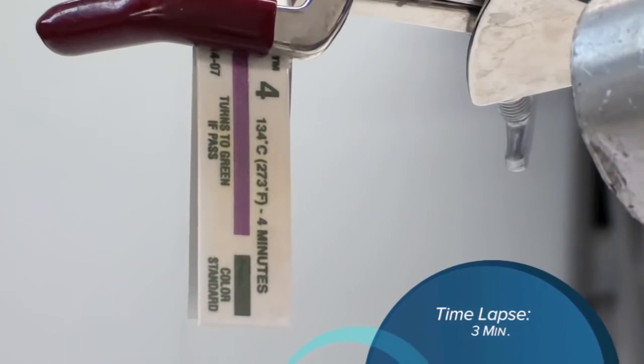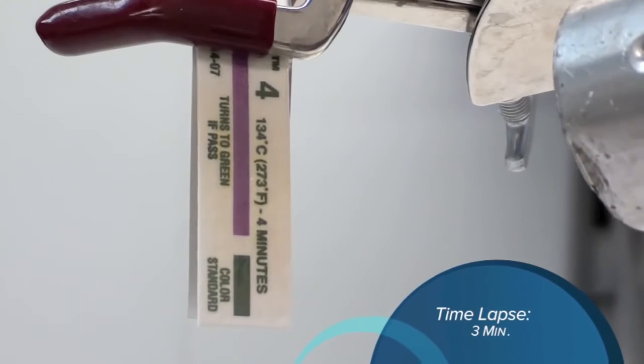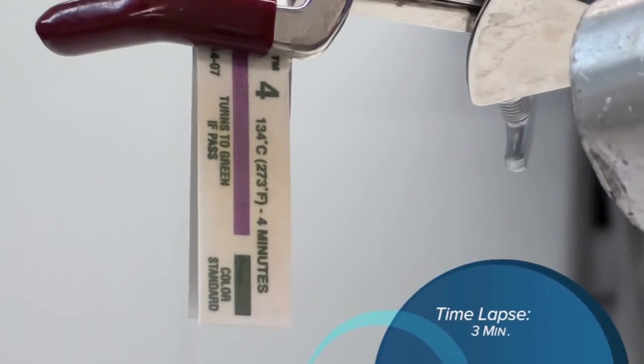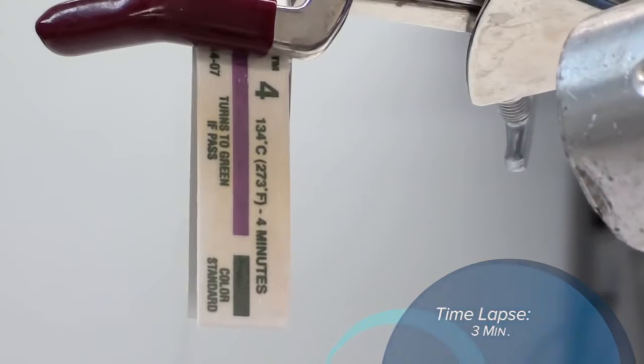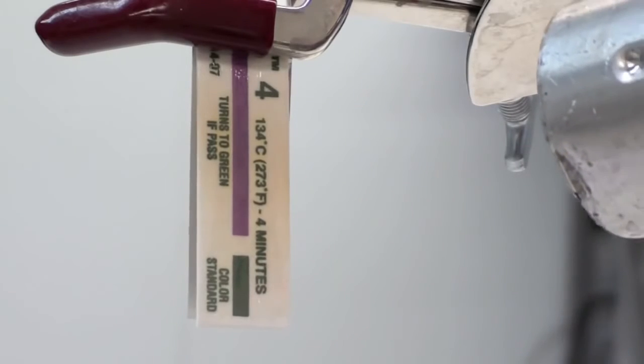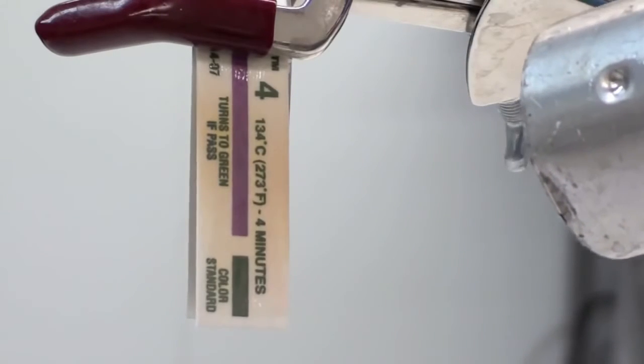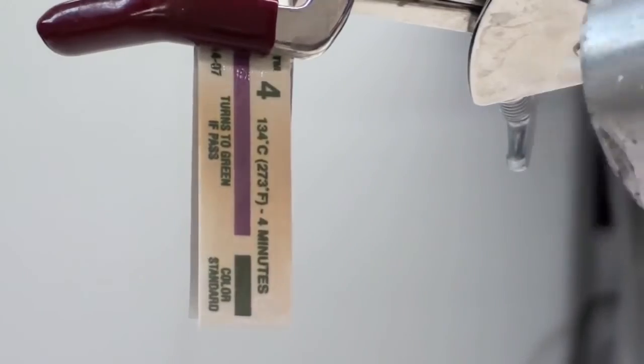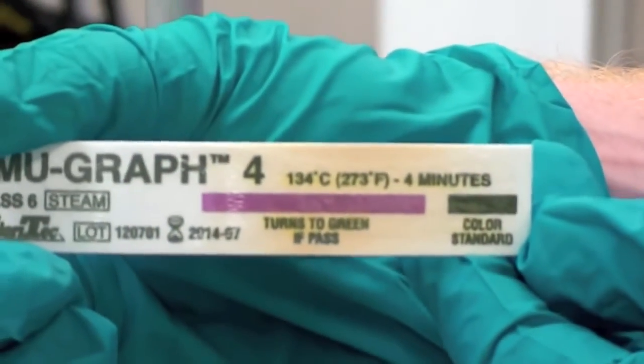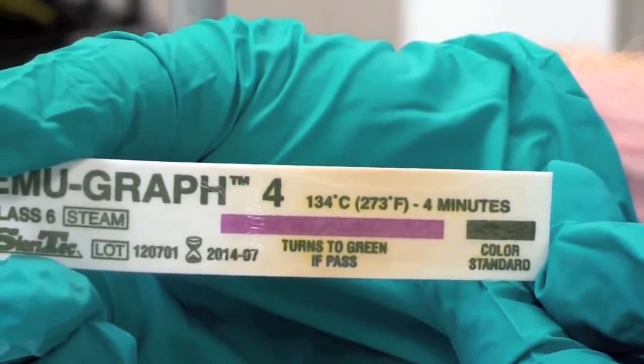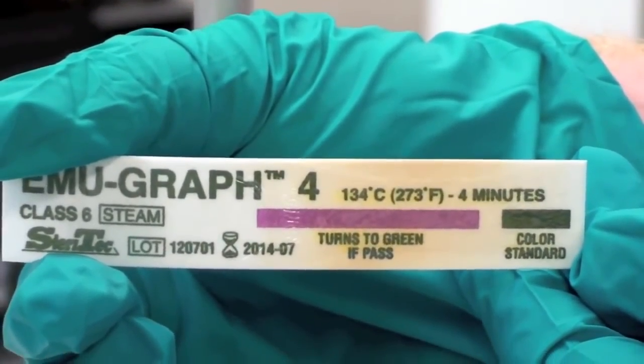We applied dry heat exposure to this indicator for 3 minutes, twice the amount of time it took for the Steris Brown indicator to change. The indicator began to burn, and the purple color remained solid. This is because there is no steam present to drive the color change. In the same real-world scenario, sterile processing professionals would immediately know sterilization conditions have not been met, effectively minimizing patient risk.